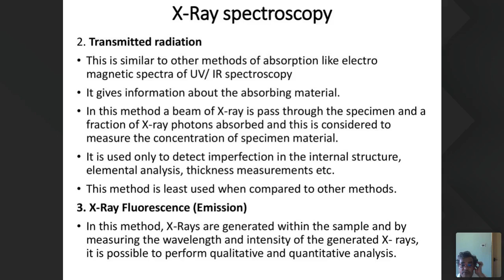X-ray fluorescence. In this method, X-rays are generated within the sample, and by measuring the wavelength and intensity of the generated X-rays, it is possible to perform qualitative and quantitative analysis. X-ray fluorescence can be considered a simple three-step process occurring at the atomic level. The incoming X-ray knocks out an electron from one of the orbitals surrounding the nucleus within an atom of the material. A hole is produced in the orbital, resulting in a high energy, unstable configuration for the atom. To restore equilibrium, an electron from a high energy outer orbital falls into the hole. Since this is a low energy position, excess energy is emitted in the form of a fluorescence X-ray.